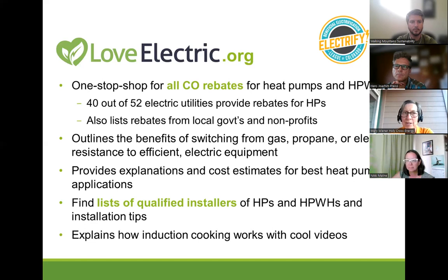And Hans really pointed out there's only a few hours, like what was it, 72 hours? Or something like that a year. There aren't many hours in the winter that your heat pump would actually not work, at least what we're seeing. We have some climates in Colorado that are worse than that. There's certainly Gunnison. I mean, Gunnison is a really cold corner of the state. Alamosa is also equally cold. So yeah, they can have 300, 400 hours that are around the limit of the heat pump. And so we look at that slightly differently and make sure it still makes sense.